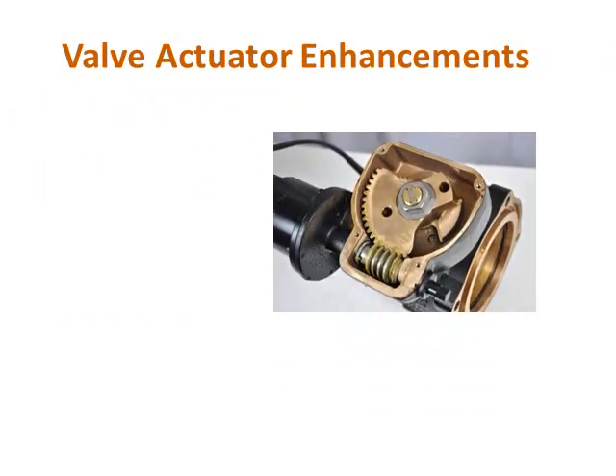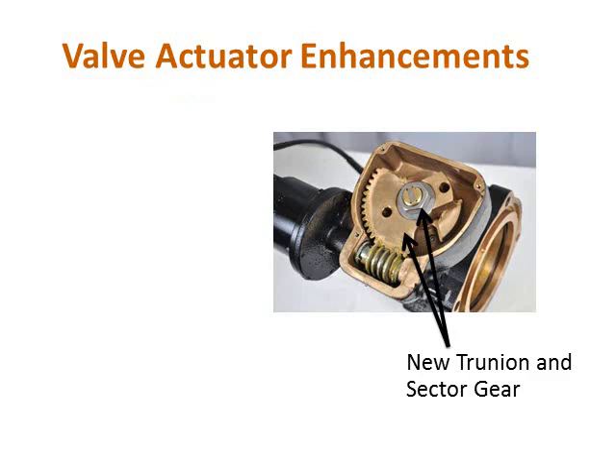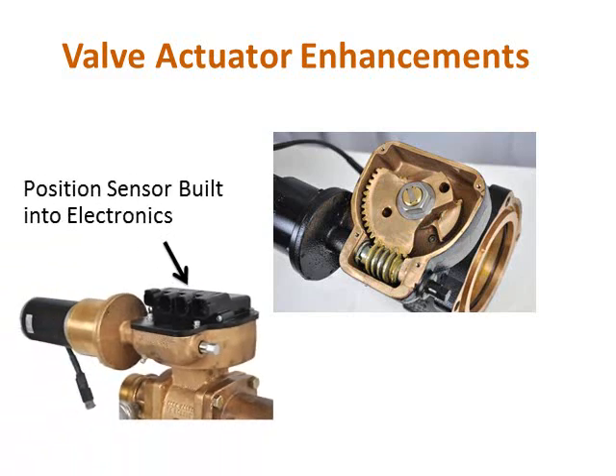Let's take a closer look at the valve actuator used with the Navigator Pro system. There are a couple key enhancements to the actuator. First, a magnet has been added to the trunnion. As the ball rotates, so does the trunnion and magnet. The trunnion and sector gear were both modified to accommodate the magnet. As the ball rotates, the sensor in the motor driver electronics senses the magnet position and knows where the ball is located at all times, providing true position feedback. This type of magnetic sensor provides easy calibration and zero maintenance, since it is non-contact and has no moving parts.